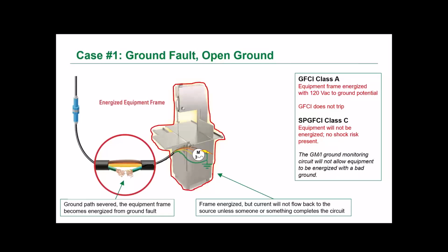Now, by comparison, the Class C special purpose GFCI would not allow this saw to be energized in the first place due to the broken grounding conductor. So that is something where the shock risk is just not even allowed to be present because that ground monitoring has taken the proactive stance of detecting that loss of ground.